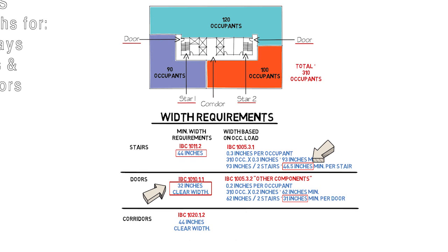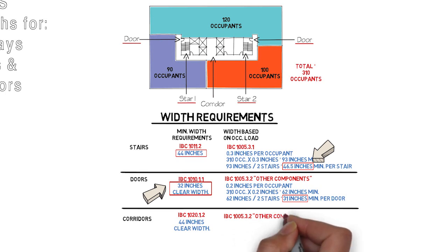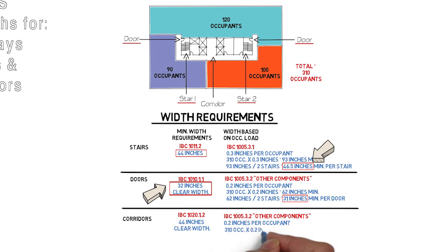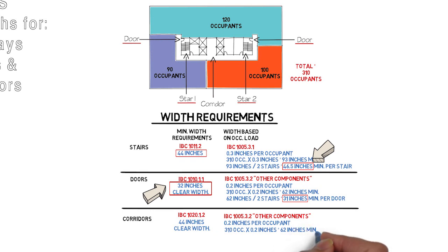Now let's proceed to calculate the required width based on occupant load. The occupant load factor falls under the same section as doors — the 'other components' section in IBC 1005.3.2. That code states that we need 0.2 inches per occupant, and we've already assessed that the calculation is 310 occupants times 0.2 inches equals 62 inches minimum. Since this is a single corridor used by all occupants to access the exits, the width of the corridor has to be the full 62 inches and not split in half.